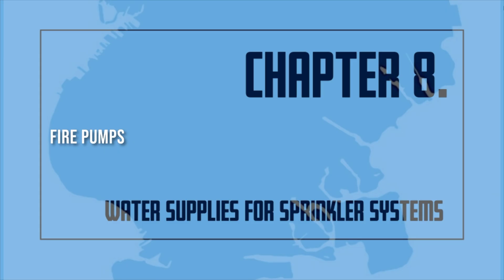Manually started pumps may be used as a secondary supply source if the primary water supply will last long enough to allow the pump to be started. This type of system gives an automatic water flow signal to the certificate of fitness holder when the pump must be started. Automatic fire pumps are usually needed where a high water demand may occur immediately. This demand may occur in a deluge system. The automatic fire pump is also used when someone is not always present to activate a manual pump.